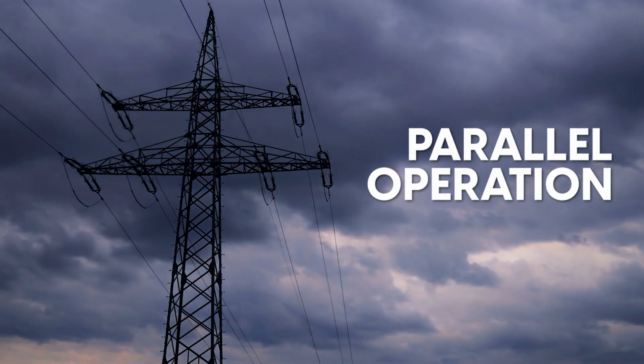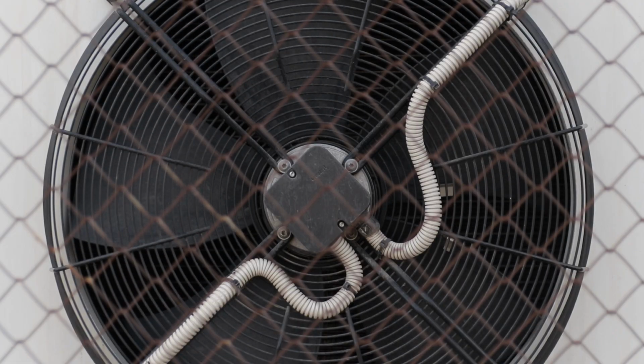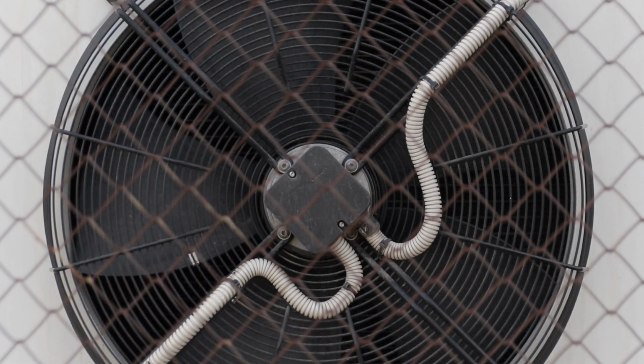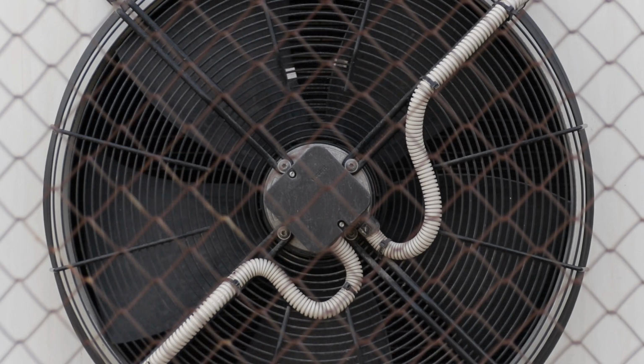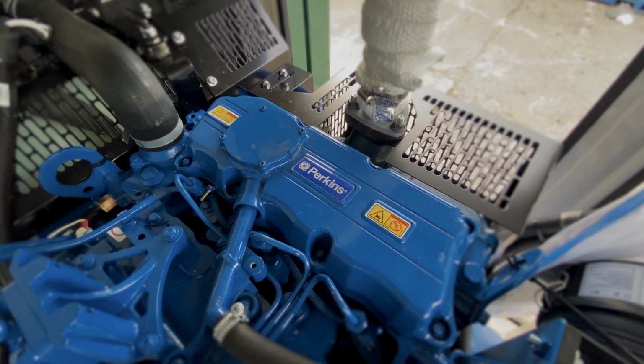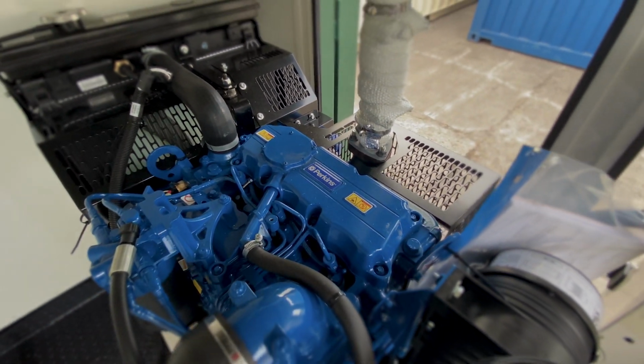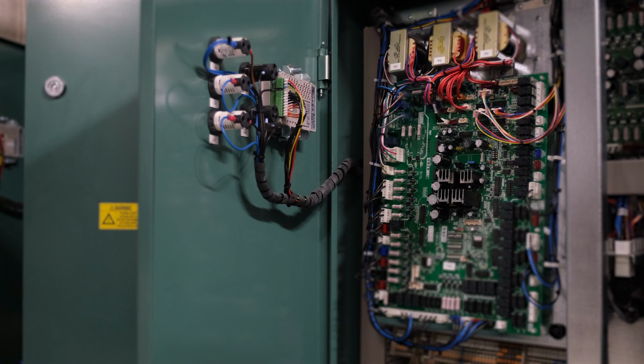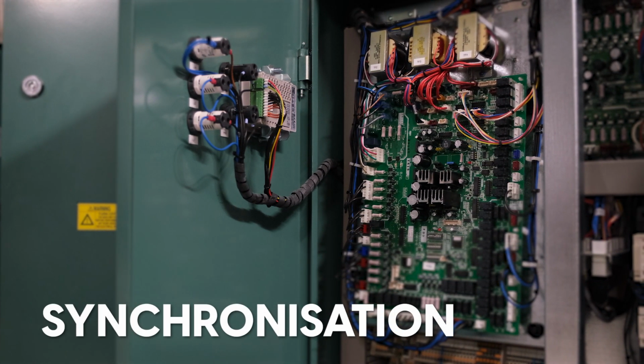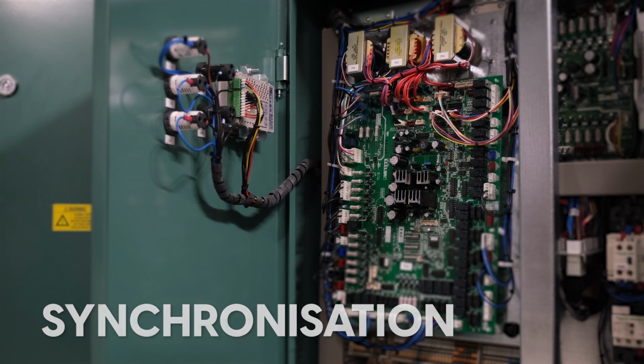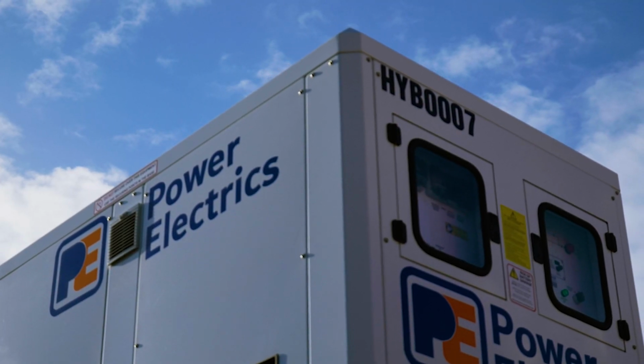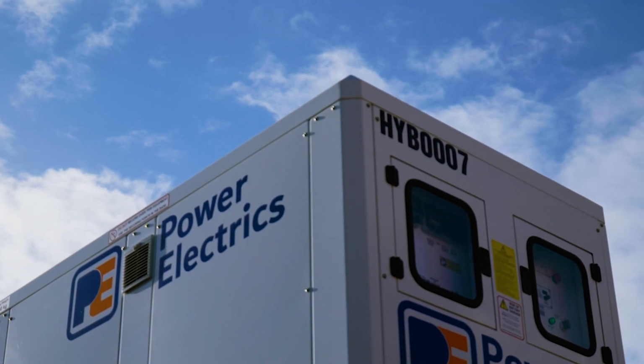Parallel operation, operating two or more generators, or generators and a network together, in order to supply a common load or power to the grid or utility. Synchronization is the process of matching the speed, frequency, and phase angles of a generator to another source, generator or mains, of the same network configuration.